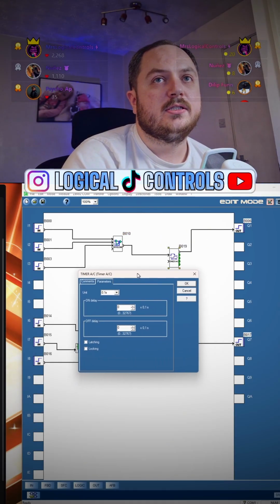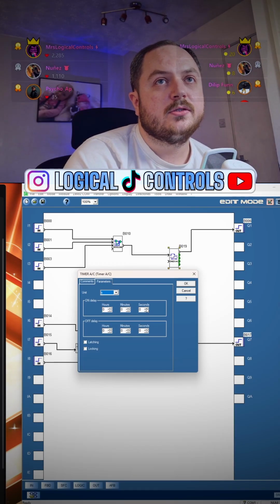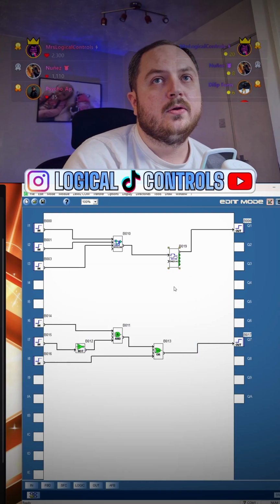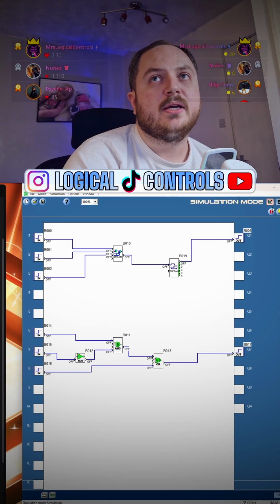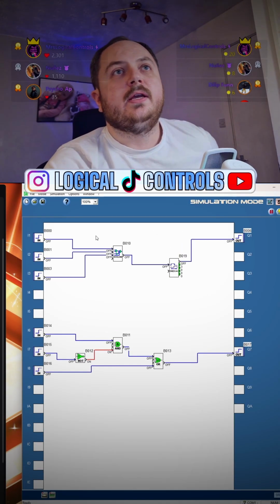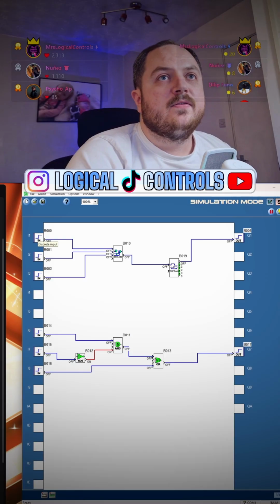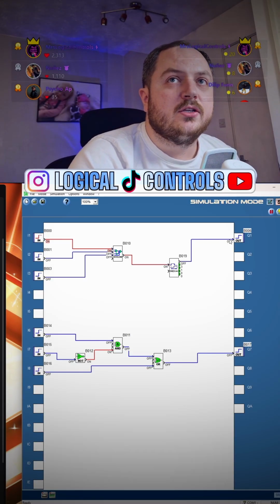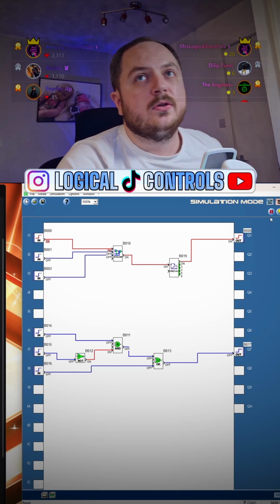Let's set this up, I normally set it in seconds. Say after 3 seconds, that's when the output will come on. Put it back into simulate, run it. If I turn my output on, you see it doesn't directly come on straight away, it waits for 3 seconds and then it comes on.